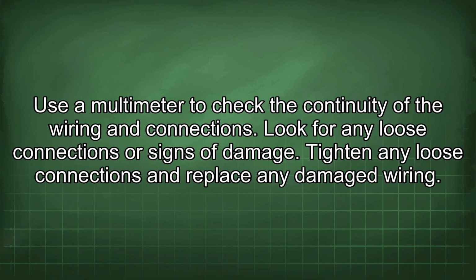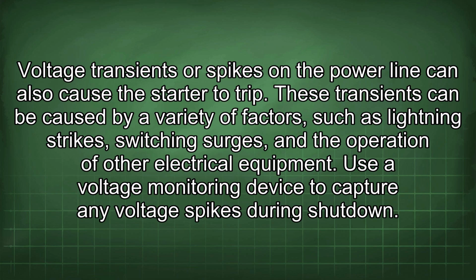Use a multimeter to check the continuity of the wiring and connections. Look for any loose connections or signs of damage. Tighten any loose connections and replace any damaged wiring. Voltage transients or spikes in the power line can also cause the starter to trip. These transients can be caused by a variety of factors, such as lightning strikes, switching surges, and the operation of other electrical equipment. Use a voltage monitoring device to capture any voltage spikes during shutdown.